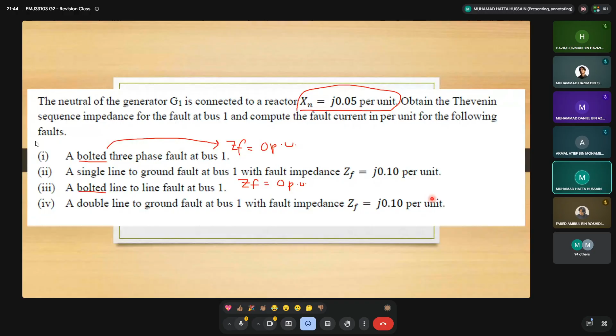So you need to obtain the Thevenin sequence impedance for the fault at bus 1 and compute the fault current in per unit for the following faults, which means that you have to find a bolted 3-phase fault at bus 1, an SLG fault at bus 1 with the fault impedance given, a bolted line-to-line fault at bus 1, where bolted means that the fault impedance is equal to 0, and a DLG fault at bus 1 with the fault impedance ZF equal to j0.1 per unit. So this is how you find it. And again, I don't want to repeat again.